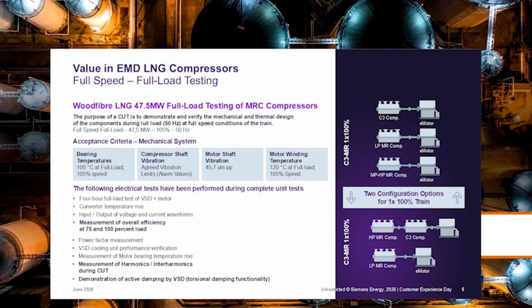So focusing back on the electric motor driven eLNG compressors, with Woodfibre, we had two configuration options, and it actually went with this bottom one here because this allows you to put two of the compressors on the same drivetrain with one motor, and then a similar sized motor for the LP mixed refrigerant. So propane and HP mixed refrigerant on one drivetrain, and then your LP mixed refrigerant compressor on the other motor. Both sized for around 47.5 megawatts, and that's at 105% full speed, full load.